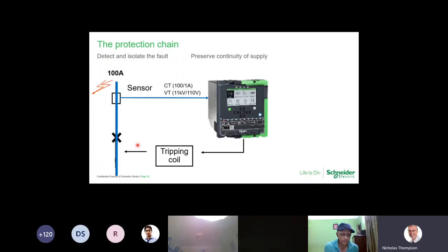So if we get a lightning strike, for instance, on the ground, we may get a very high voltage that will somehow flow through into the network, and if we're using VTs and we're using voltage protection as well, then the VT will pick up a voltage rise, and if we've got that particular protection scheme in play, it will then trip the circuit breaker because of a very high voltage rise. But here I'm using the example of a very high current.